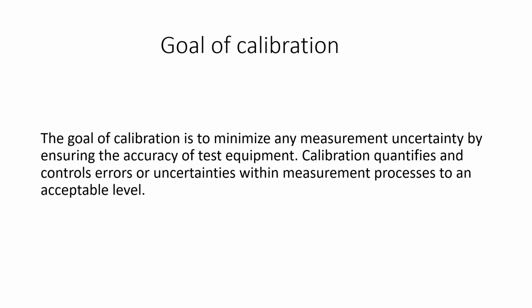Goal of calibration. The goal of calibration is to minimize any measurement uncertainty by ensuring the accuracy of the test equipment. Calibration quantifies and controls errors or uncertainties within the measurement process to an acceptable level.